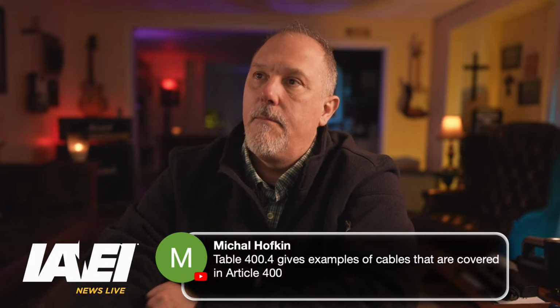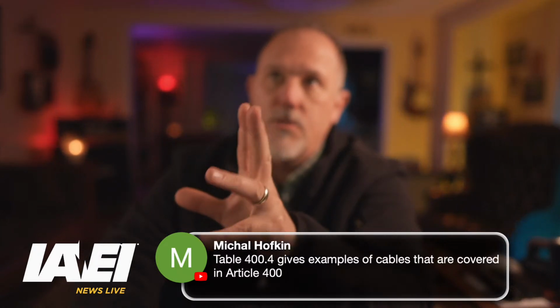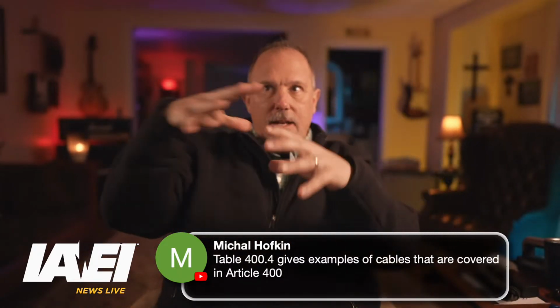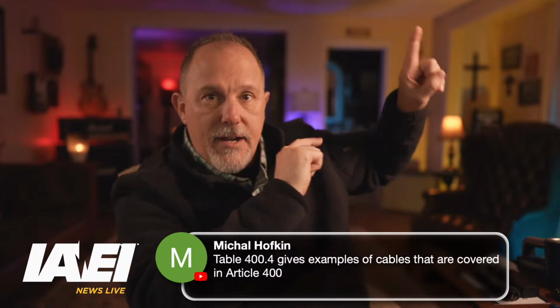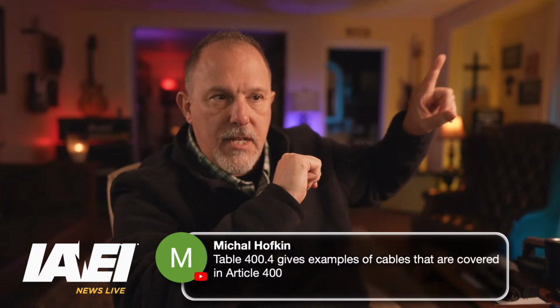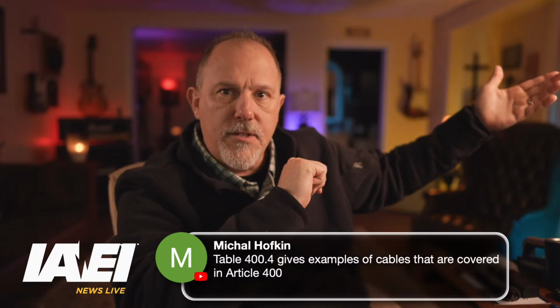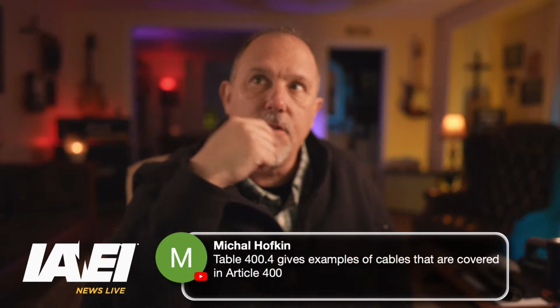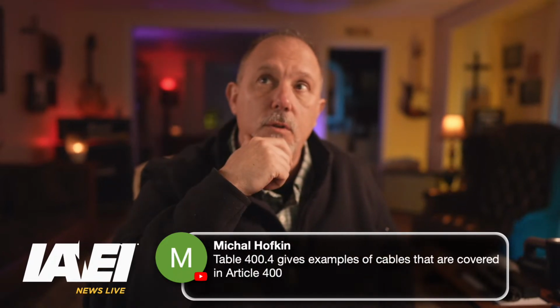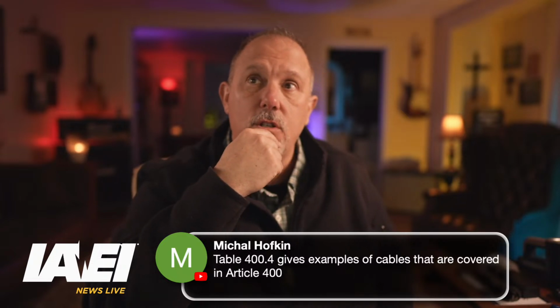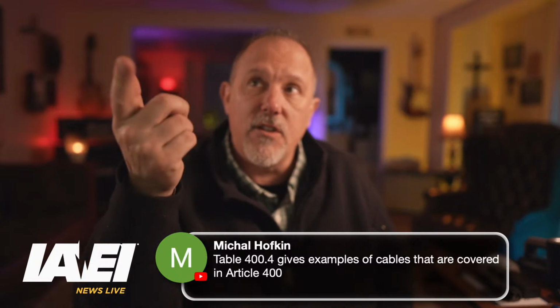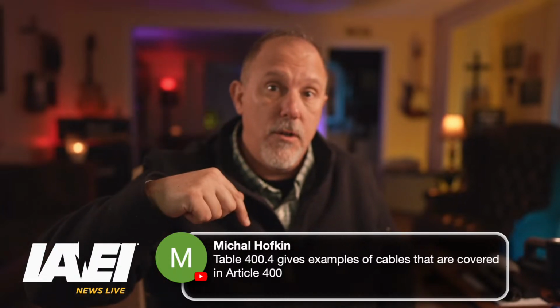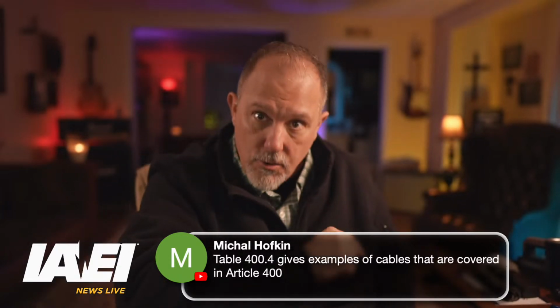But you would go to those articles -- so once you've identified the conductor, say you're looking at a pendant, you ask what are the code requirements for this, and you look in chapter 3, can't find anything, then you go to chapter 4, equipment for general use, and you find fixture wires and flexible cords and flexible cables. Figure out which one of those two articles pertains to your application.